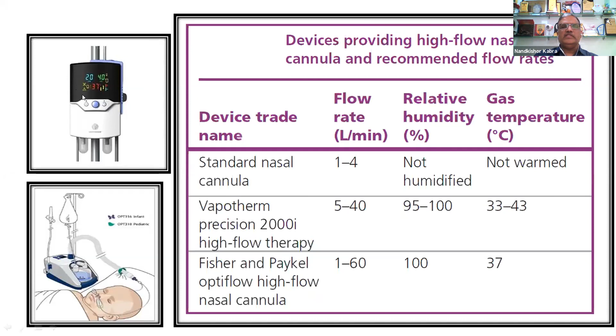We were all familiar with the bubble CPAP system of Fisher-Paykel, and if you just connect the front end of the inspiratory limb to an OptiFlow nasal cannula, we can use that as a high flow nasal cannula. You can give flow from 1 to 60 liters and 100% humidity is possible. Usually gas is heated to about 37 degrees. The newer version of the Fisher-Paykel device is called Airvo 2. There, it can be used in all age groups from newborn to pediatric to geriatric. And what you are seeing here is a Vapotherm device.